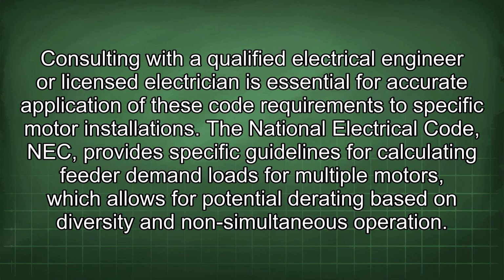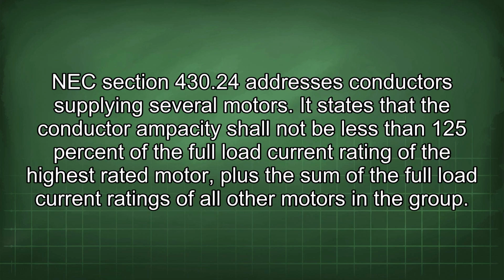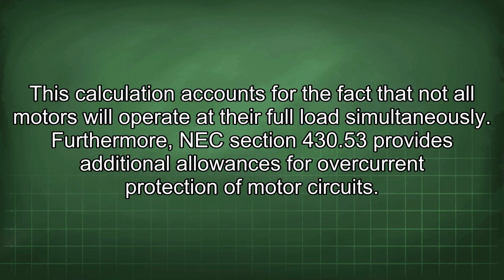The National Electrical Code (NEC) provides specific guidelines for calculating feeder demand loads for multiple motors, which allows for potential derating based on diversity and non-simultaneous operation. NEC Section 430.24 addresses conductors supplying several motors. It states that the conductor ampacity shall not be less than 125% of the full load current rating of the highest rated motor, plus the sum of the full load current ratings of all other motors in the group. This calculation accounts for the fact that not all motors will operate at their full load simultaneously.